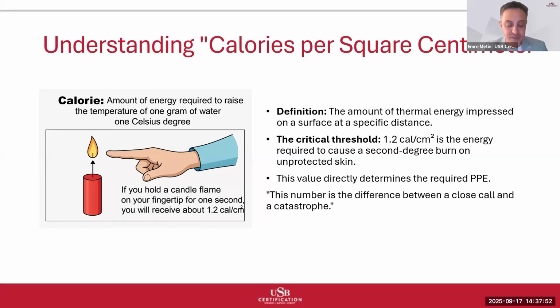When we specify PPE requirements, we are essentially asking how much energy this protective system can absorb and dissipate before allowing 1 calorie per square centimeter to reach the worker's skin. This is why I say that the incident energy calculation is literally the difference between a close call and a catastrophe. A location with 15 calories per square centimeter incident energy will cause severe, potentially fatal burns to unprotected workers. The same location with properly selected and worn 25 calories per square centimeter PPE will result in no thermal injury. Understanding this energy concept is fundamental to making informed protection decisions.